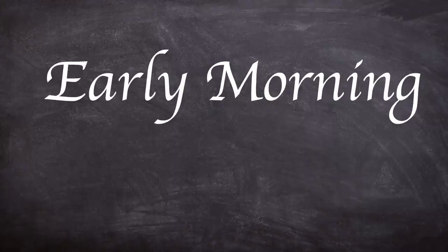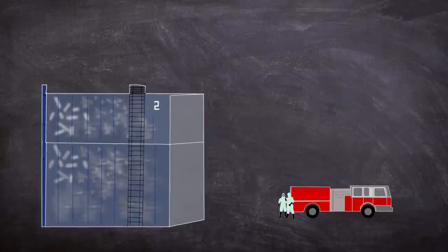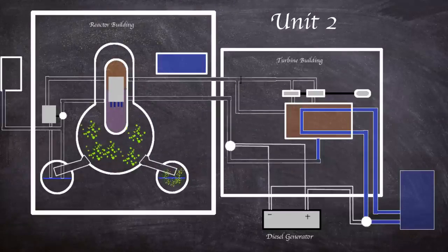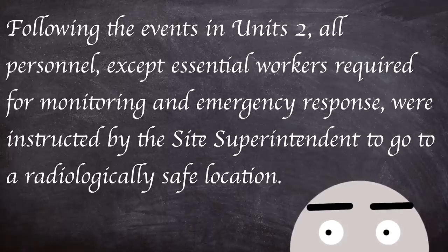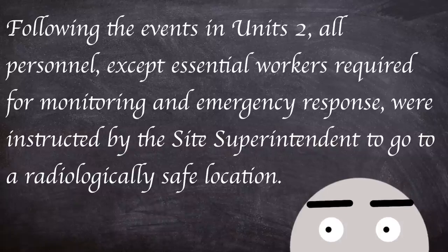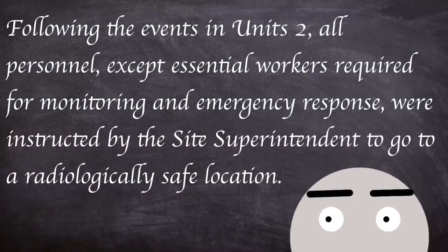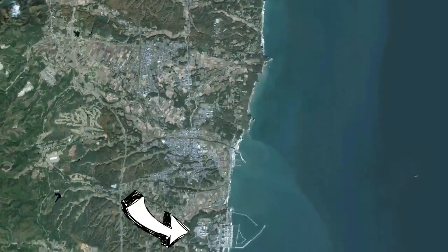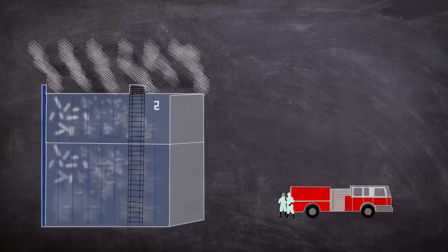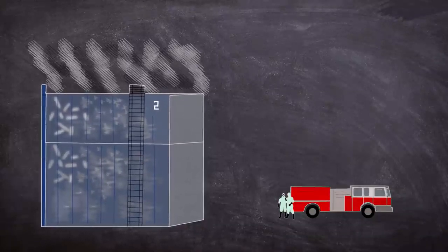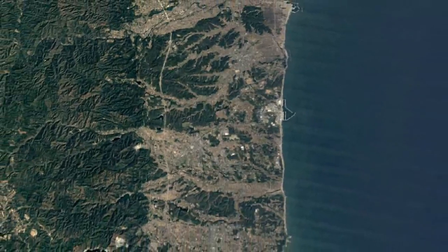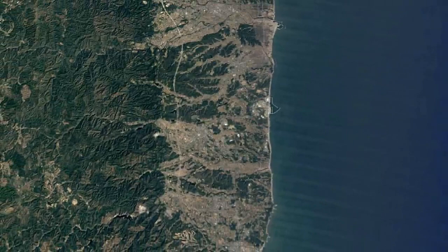In the early hours of the 15th of March, explosions were heard at units 2 and 4, with the top half of unit 4's building being damaged. A drop in pressure readings on the suppression chamber of unit 2 was seen. This hinted that the containment of the reactor had been compromised, meaning an uncontrolled release of radioactive isotopes. Following the events in unit 2, all personnel except essential workers required for monitoring and emergency response were instructed by the site superintendent to go to a radiologically safe location. 650 people evacuated to Fukushima Daini nuclear power plant site approximately 12km away. White smoke or steam was seen to be coming from the top of unit 2's reactor building. A radiation measurement was taken of 11.93 millisieverts an hour at the main gate at 9am. An order was issued by the government authorities at 11am requiring all residents within a 30km radius of the power plant to take shelter indoors.